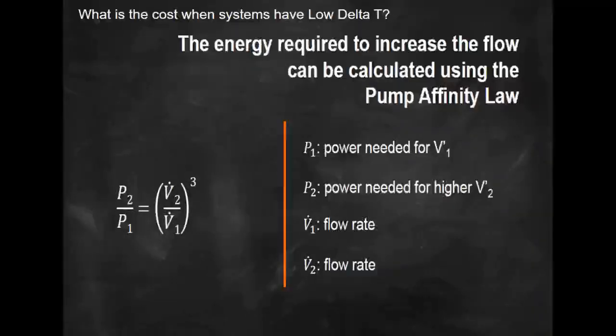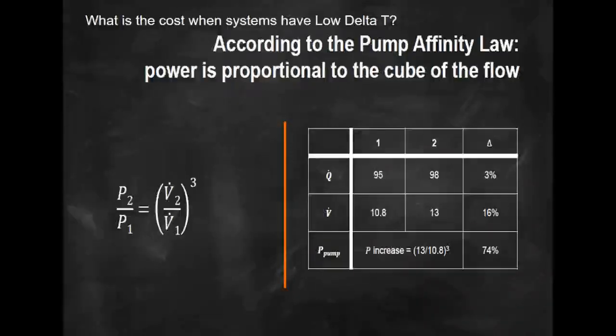If we look at calculating the energy required to increase that overflow we just witnessed, then we can use the pump affinity law to calculate it. We can look at the flow rate that we've designed, which is 10.8, and that should give us our 95 kilowatts of cooling. But we weren't able to control that particular coil to 10.8. We let it go to 13. We didn't see it, it's invisible. And it gave us 3 kilowatts of cooling more. You probably wouldn't notice it in a room. But that actually is 16% more water and 3% more cooling.